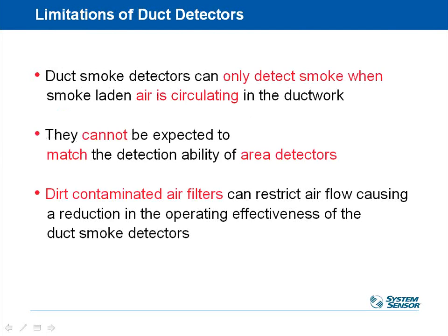Okay, so obviously a duct smoke detector being mounted in the duct only works when the fan is running. If the fan is off, like at nighttime, we often shut our air handlers down. It'll take a long time for smoke to get from the space into the duct and over to the detector. So that's another reason why we don't want to use it in place of the normal systems, because it'll take a long time when the air handler is off. So it's got to be running in order to sense that.